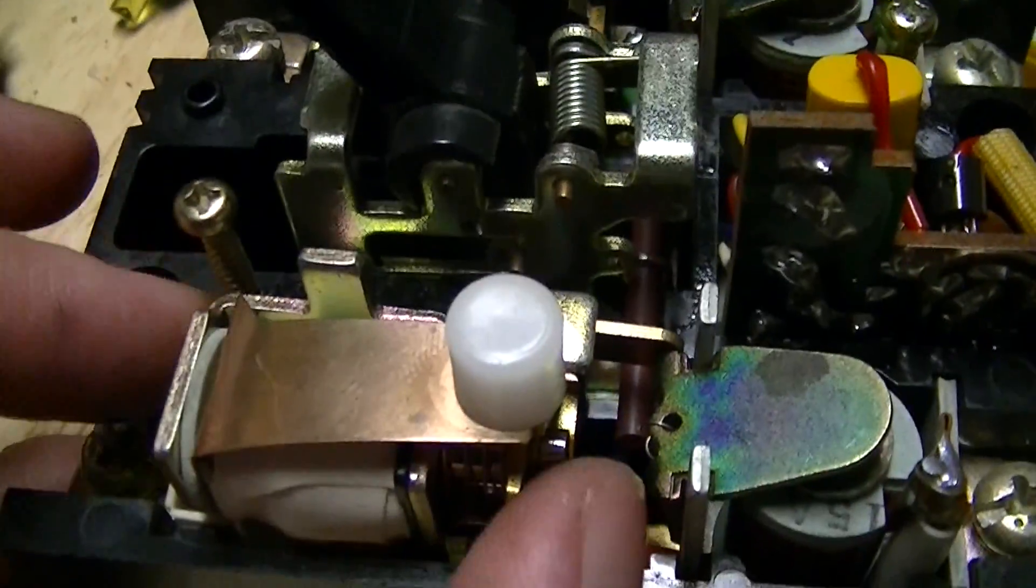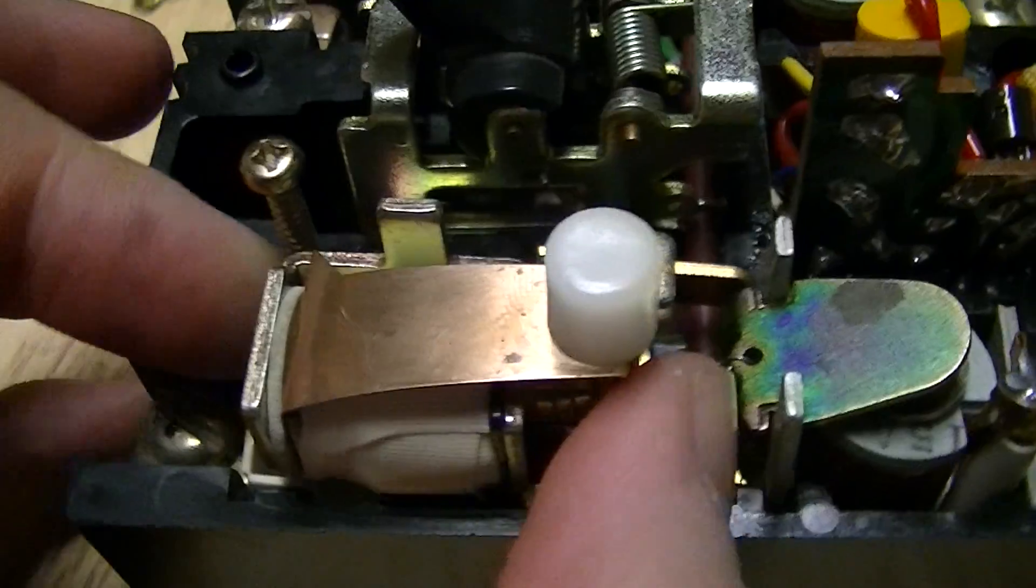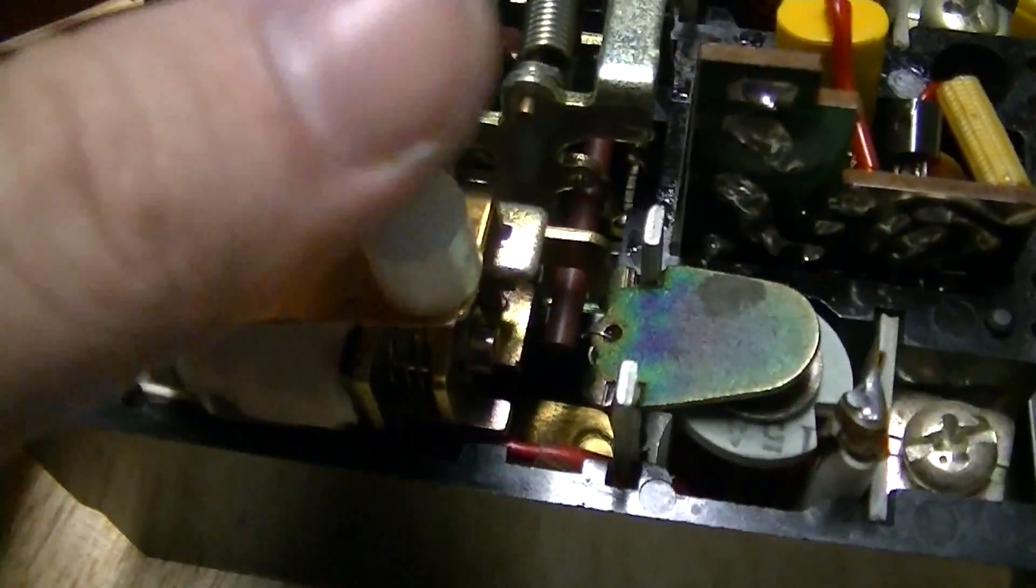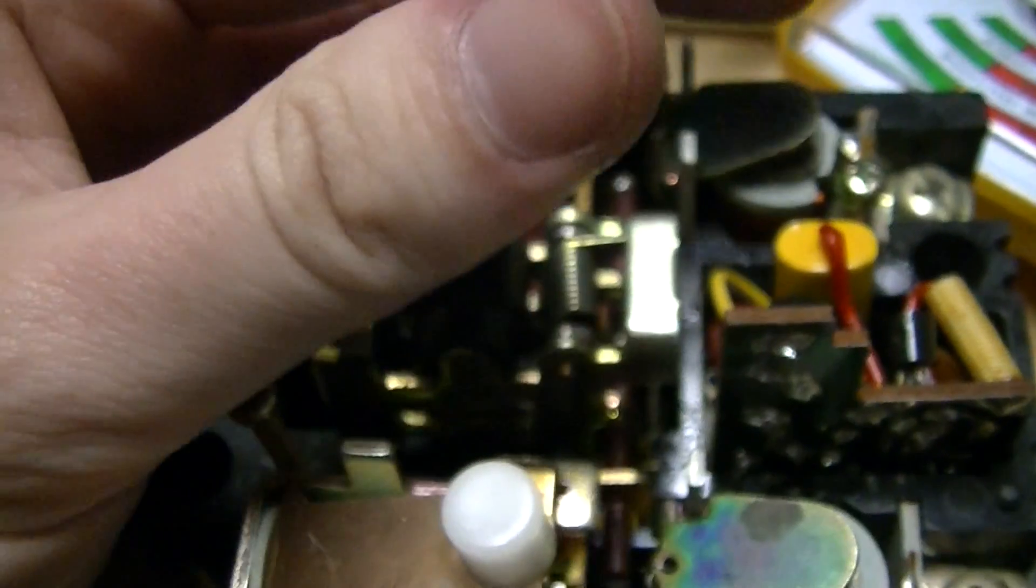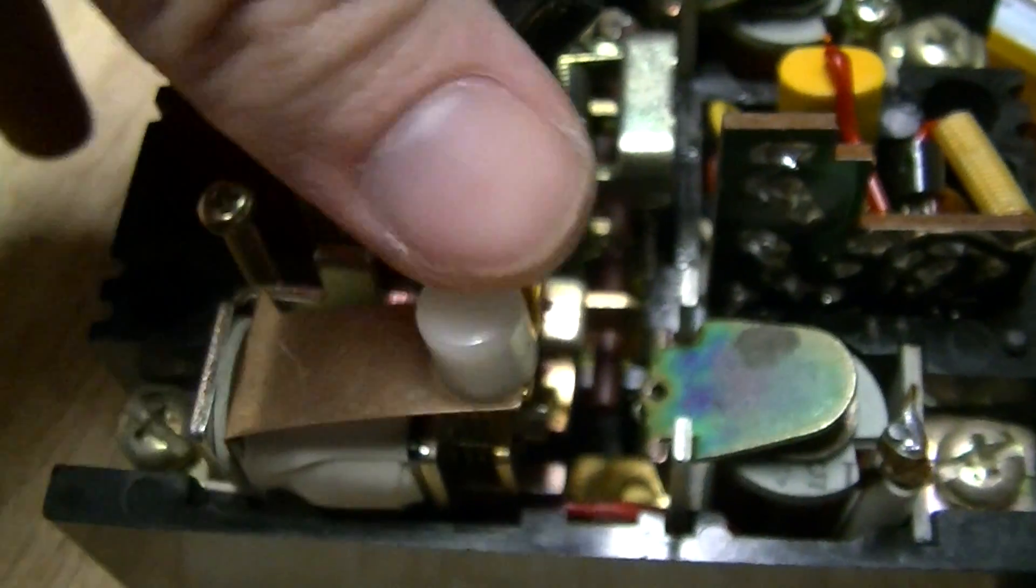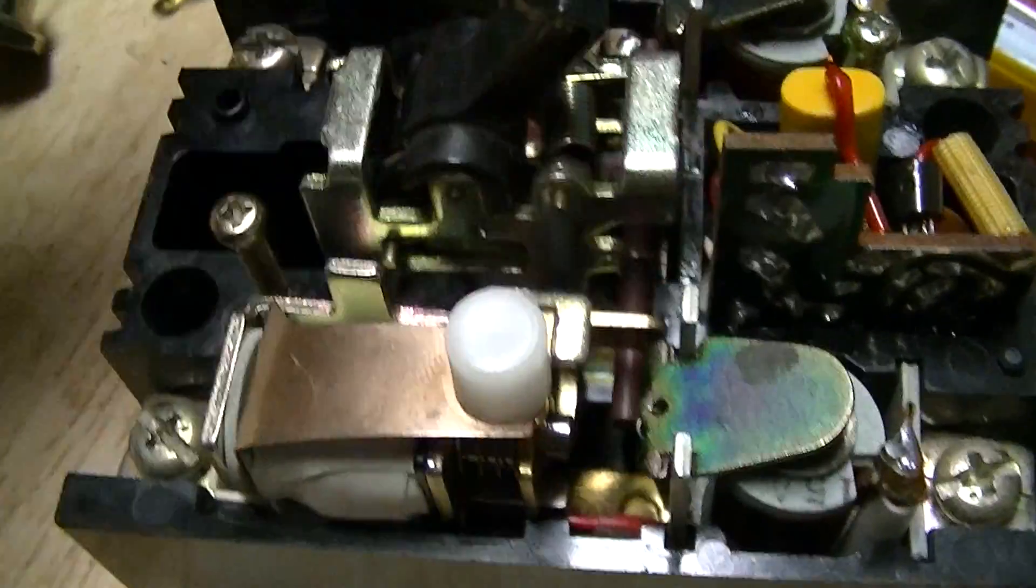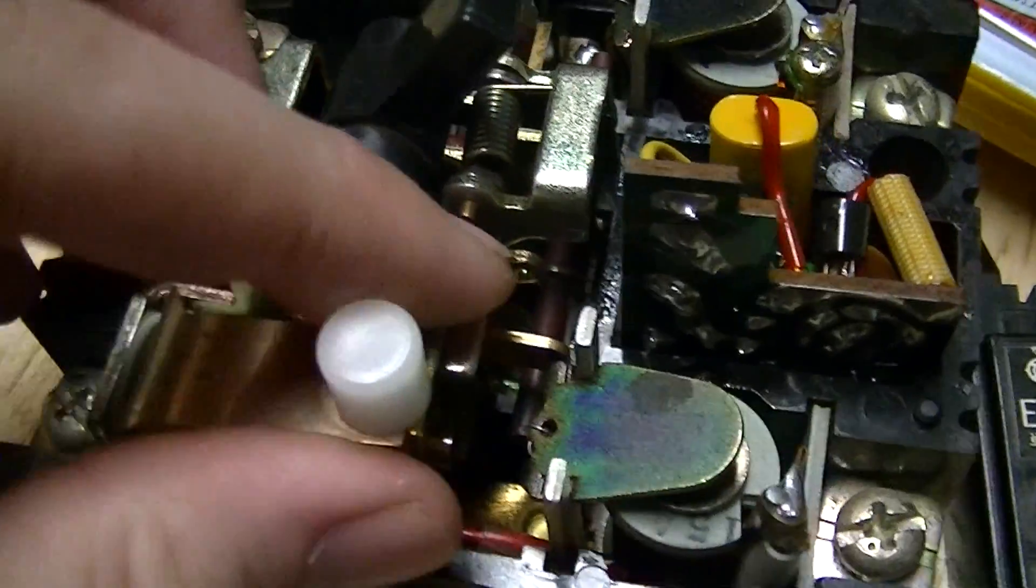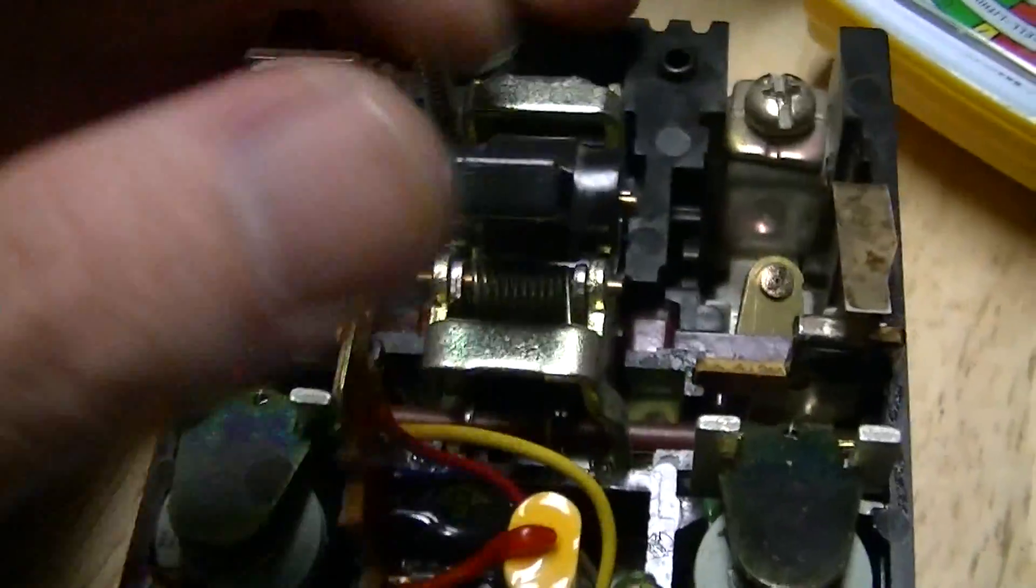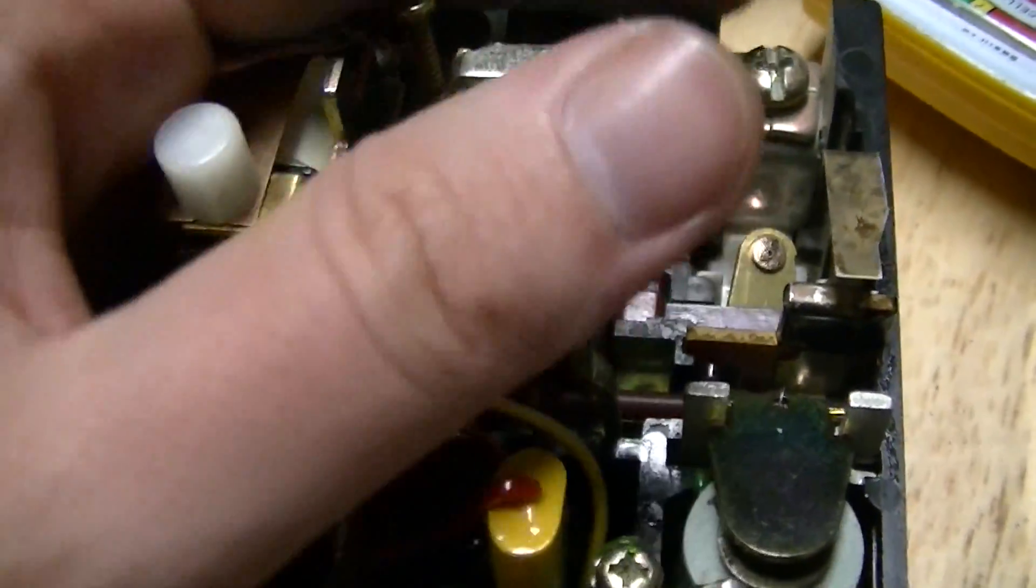In the event of a ground fault, this solenoid is activated by the protection circuit, tripping the device but also popping up this button. That means that the device cannot be turned back on, or the breaker cannot be turned back on, until this button is pressed, clearing or resetting the trip and re-engaging the switch mechanism.